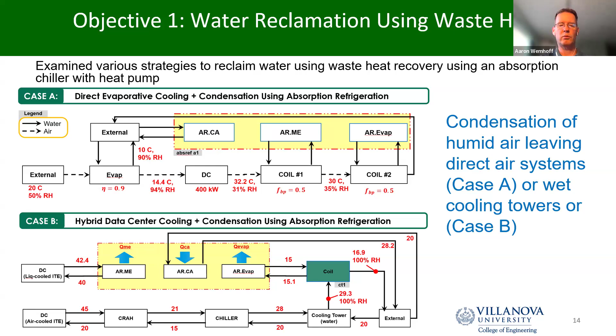So all these are condensation based. Case B is what we'll call a hybrid data center, where some of the equipment inside is liquid cooled and some is air cooled. You can see the liquid cooled ITE feeds into the micro evaporator, and essentially the output of the cooling tower, that humid air plume, interacts with a coil connected to the evaporator. So again, we have condensation based water removal.